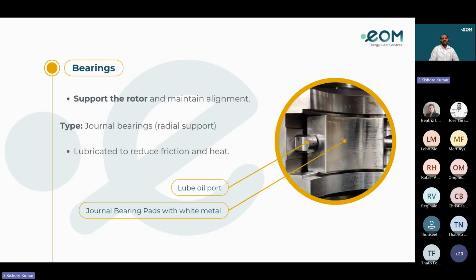Bearings. Coming to the bearings, these are the white metal bearings, also called Babbitt bearings, a critical component in steam and gas turbines, where they provide low friction, high load support to the rotating shaft or rotor. These bearings are lined with a thin layer of white metal alloy, which includes tin, lead, antimony, and copper, giving them excellent properties for lubrication and durability under high speed and high load conditions. Basically, it supports the rotor and maintains the alignment.